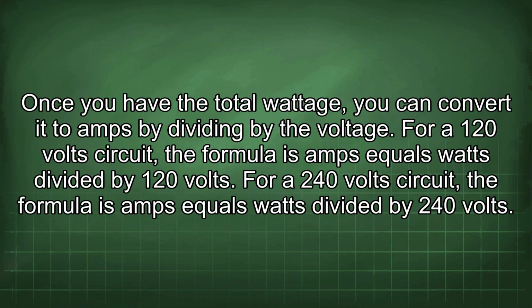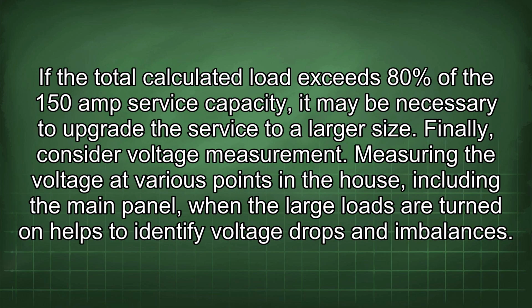Once you have the total wattage, you can convert it to amps by dividing by the voltage. For a 120 volt circuit, the formula is amps equals watts divided by 120 volts. For a 240 volt circuit, the formula is amps equals watts divided by 240 volts. If the total calculated load exceeds 80% of the 150 amp service capacity, it may be necessary to upgrade the service to a larger size.